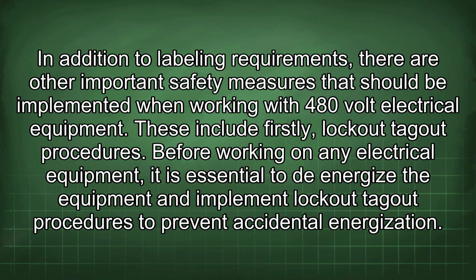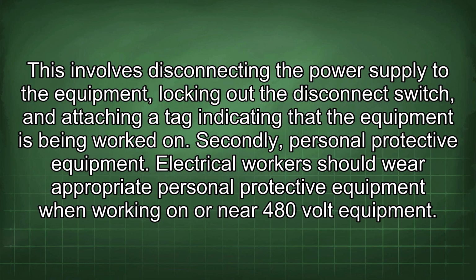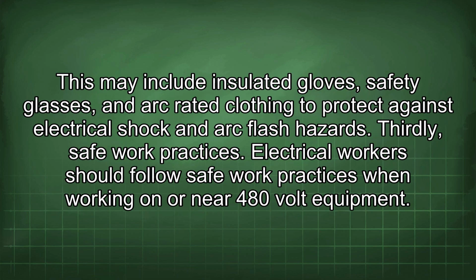In addition to labeling requirements, there are other important safety measures that should be implemented when working with 480-volt electrical equipment. These include, firstly, lockout-tagout procedures. Before working on any electrical equipment, it is essential to de-energize the equipment and implement lockout-tagout procedures to prevent accidental energization. This involves disconnecting the power supply to the equipment, locking out the disconnect switch, and attaching a tag indicating that the equipment is being worked on. Secondly, personal protective equipment. Electrical workers should wear appropriate personal protective equipment when working on or near 480-volt equipment. This may include insulated gloves, safety glasses, and arc-rated clothing to protect against electrical shock and arc flash hazards.